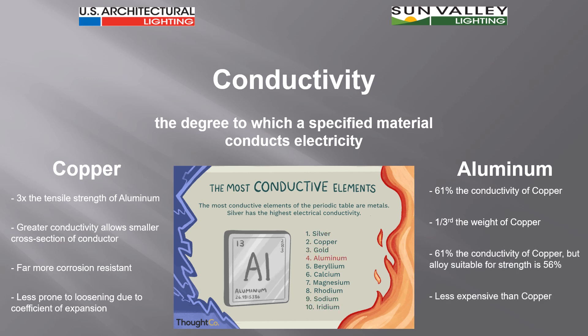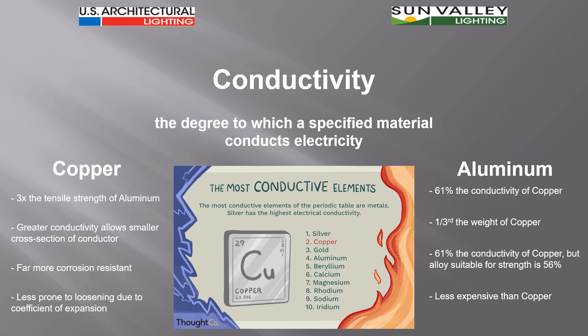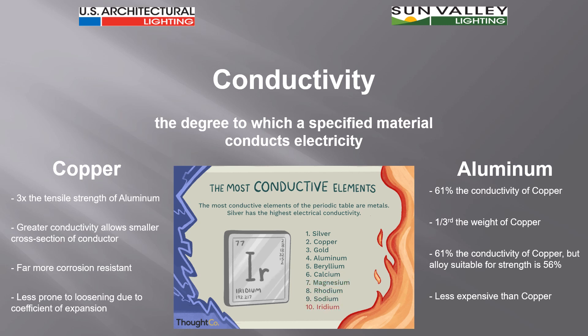Normally, aluminum used in lighting fixtures is not raw aluminum. Raw aluminum is too soft, galls too easily, and doesn't machine smoothly, so there are always additives creating aluminum alloys. Alloys of aluminum — which include mixtures with silicon, magnesium, or zinc — cause aluminum to be less conductive. Typically, aluminum alloys are only about 56%, or about half, the conductivity of copper. This is another reason it tends to be used less for everyday wiring than copper, although aluminum is much less expensive — perhaps a third or a quarter of the cost.